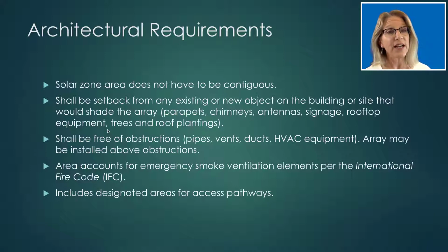A designated area needs to be set back from any existing or new object on the building or the site that would shade the array. So this would include things like parapets, chimneys, antennas, signage, any kind of rooftop equipment, and even trees, either on site or on the roof, as well as roof plantings. The area shall be free of obstructions, and we're referring to things like pipes, vents, ducts, HVAC equipment.